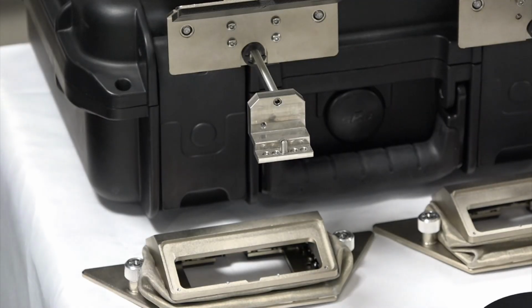This positioner will be used with a variety of probe stations, but these probe stations have the capability of changing in temperature. This is fine when we reach higher temperatures, but lower temperatures are more tricky. Also, we may have devices which don't want light ingress, so we want to have a sealed environment. The sealed environment also allows us to have dry gas inside, which prevents moisture forming on the wafer and ultimately freezing. In order to have a sealed environment, you'll see in a moment the top hat, but the top hat has seals which attach between it and the positioner.